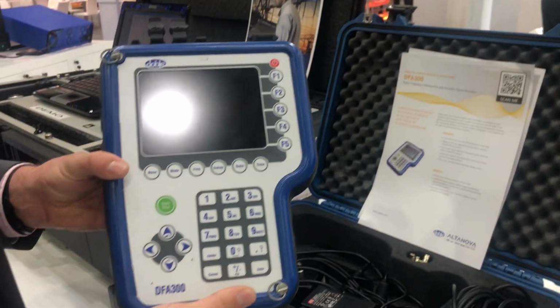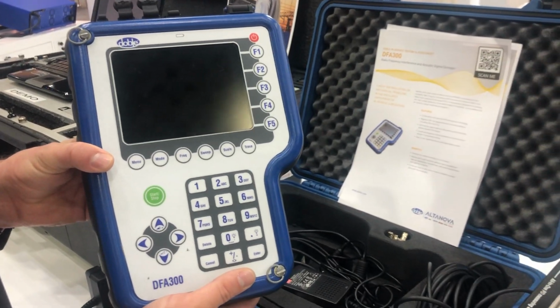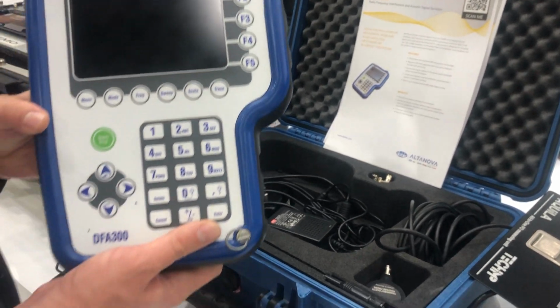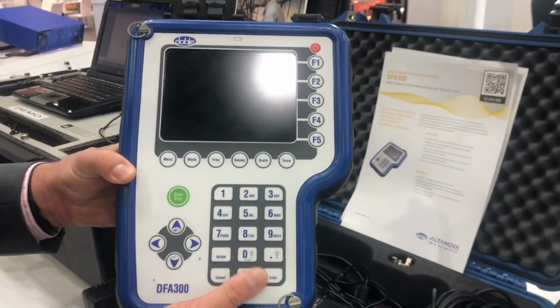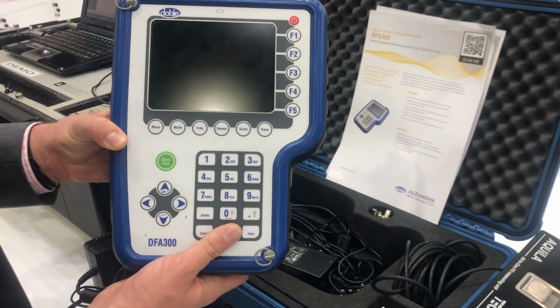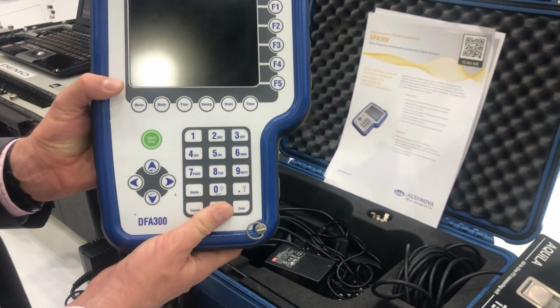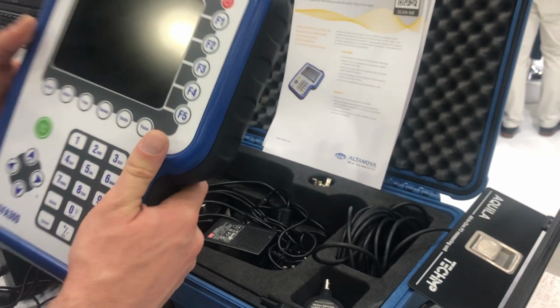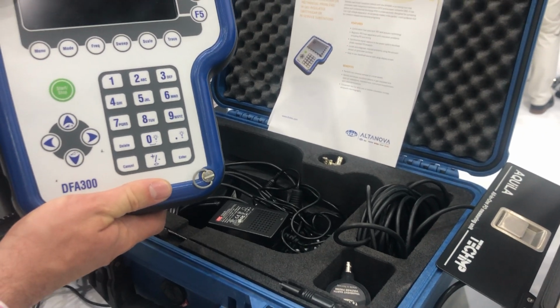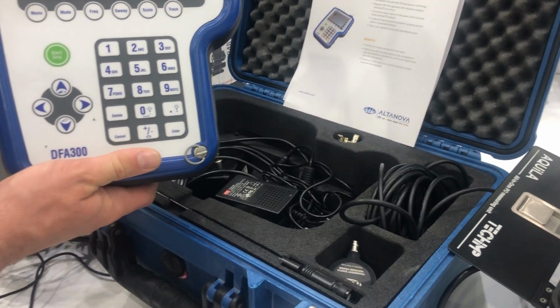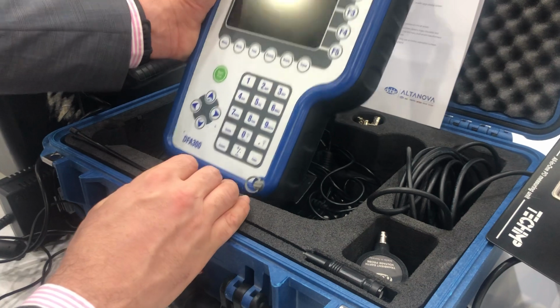Of course, a fantastic device from Doble, a DFA 300, would be also a partial discharge tester with a plethora of different sensors. You can also test PD on many types of assets. You see that it's more portable than Aquila. You can hold it like this and carry it around. So with the DFA, you test partial discharge in the substation.